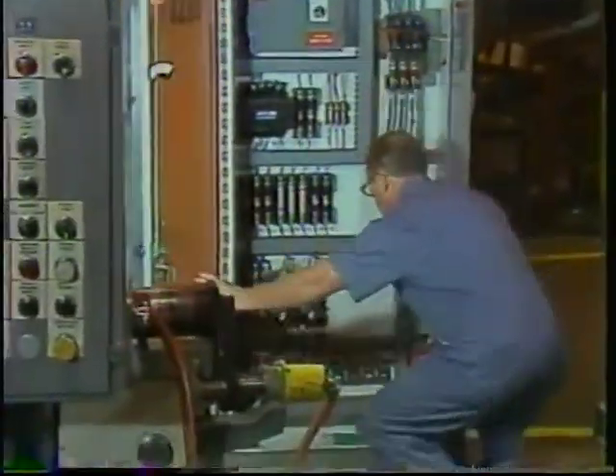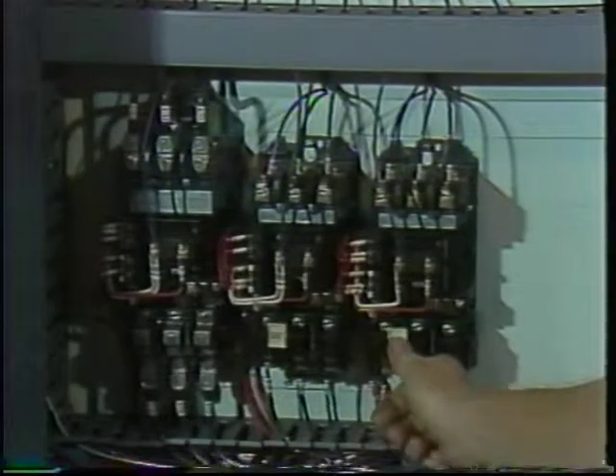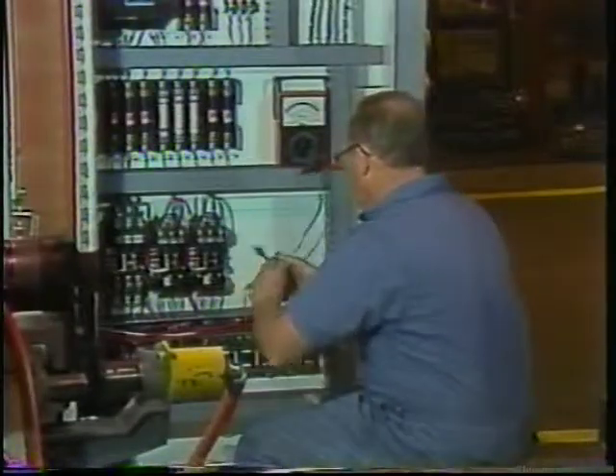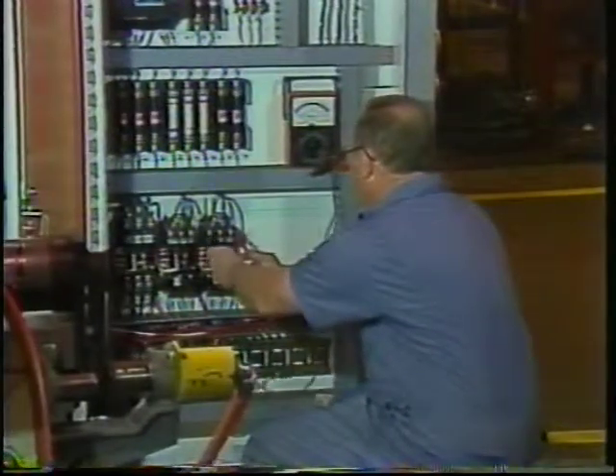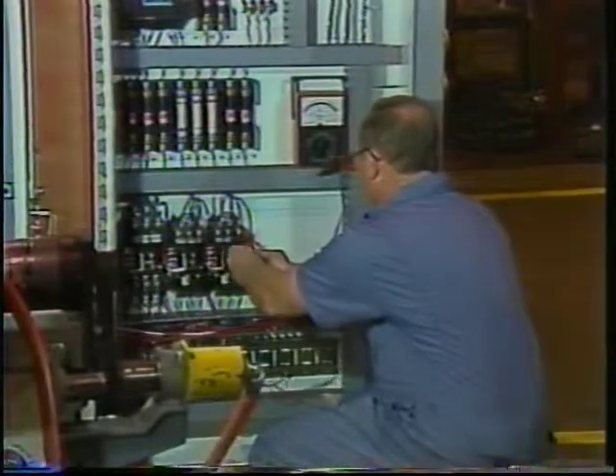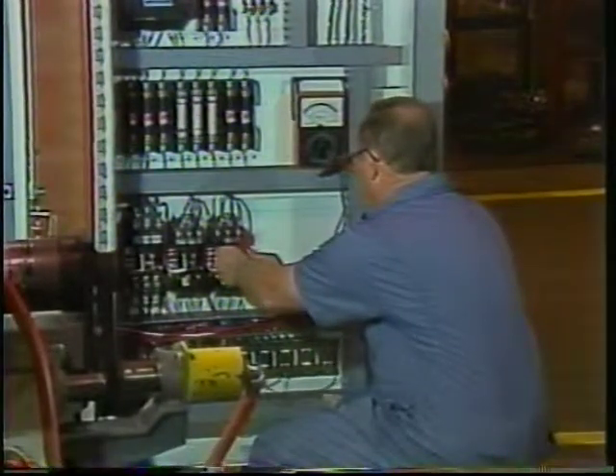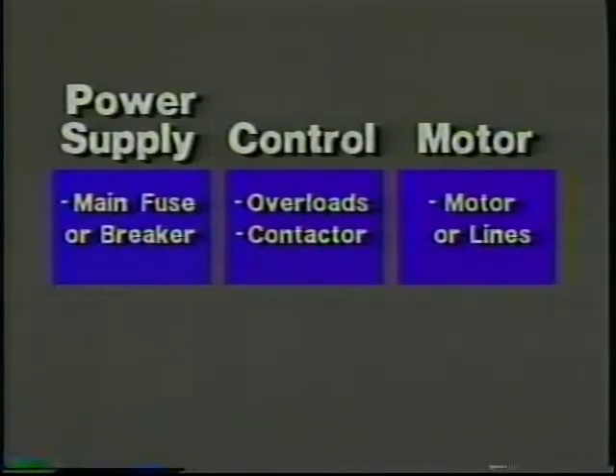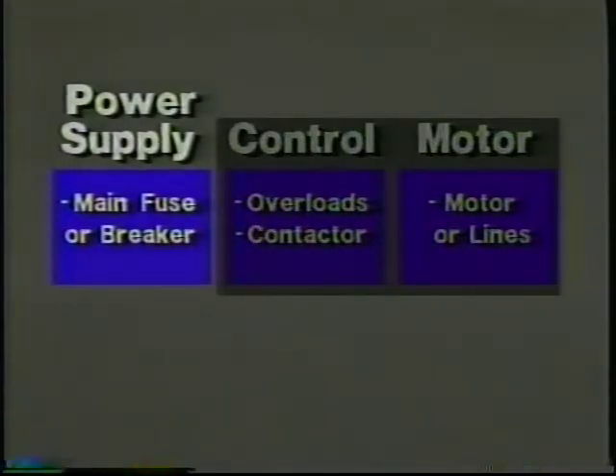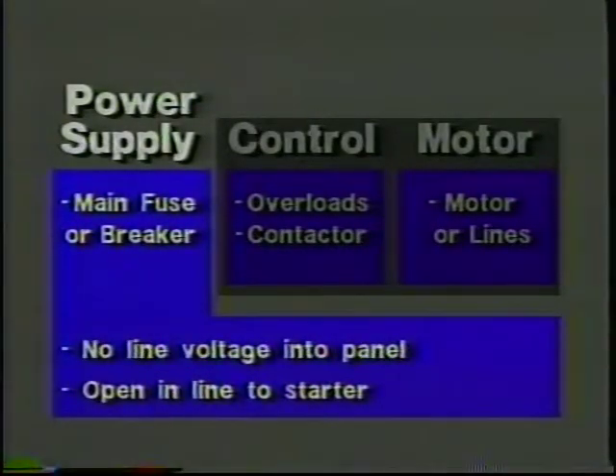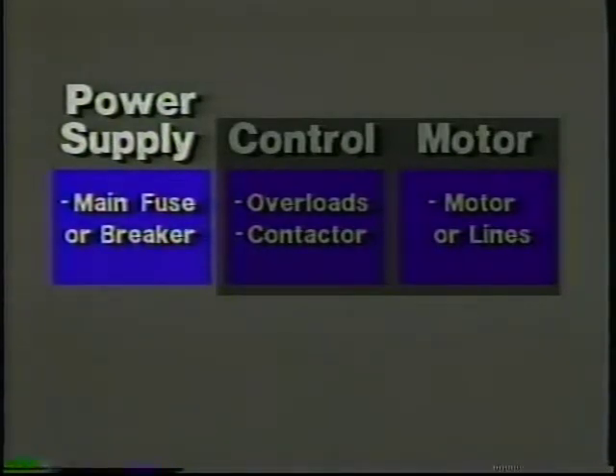Chances are they will not be tripped, since their job is not to protect the motor against this kind of fault. Again, you would go to the voltage on the input side of the contactor. This time, however, you would find no voltage, and this indicates a problem somewhere in the power supply. Now, what are the probable causes? It is unlikely, but possible, that there is no line voltage coming into the main panel. It is also possible that there is an open in the lines to the starter. But by far the most likely possibility is a blown main fuse or tripped circuit breaker.